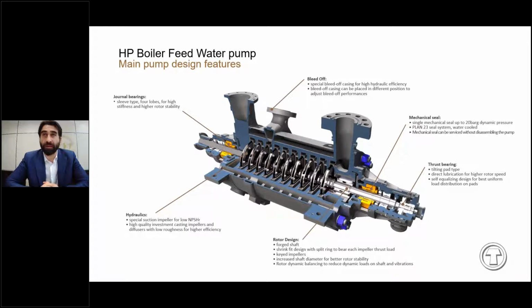After the first impeller, there are 2 stages before the bleed-off casing, and then there are 7 stages after the bleed-off casing. The bleed-off connection is used to take a part of the flow, at the pressure of the 3rd stage, in order to feed the medium pressure circuit of the boiler. However, the pressure of the bleed-off can be changed simply by changing the position of the bleed-off to a different stage, or by changing the type and geometry of the impeller before the bleed-off.